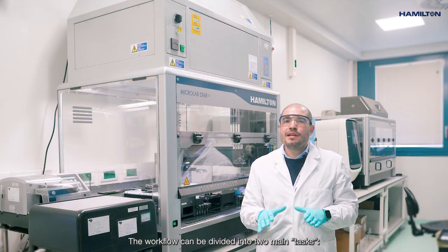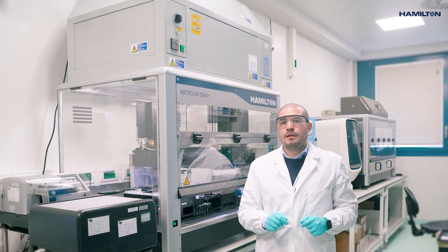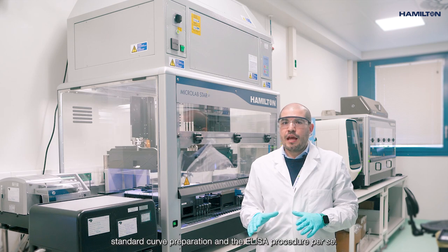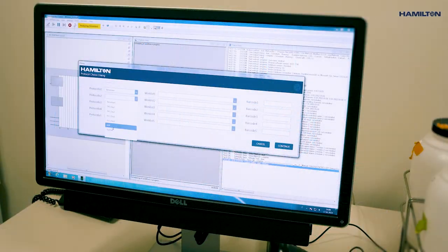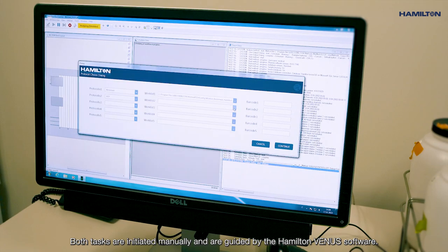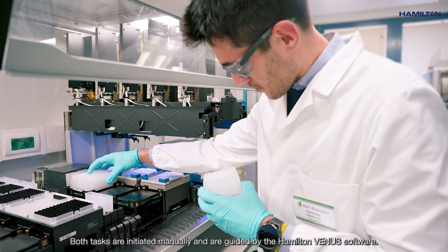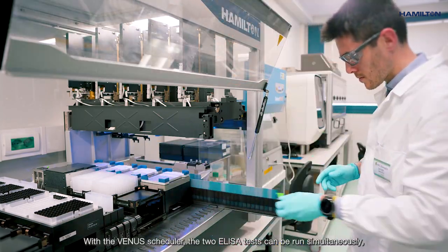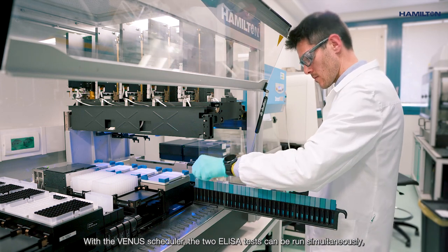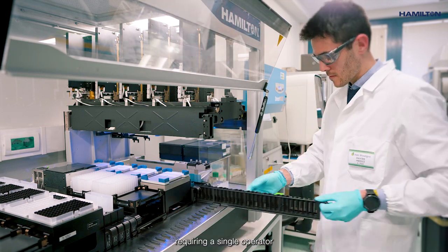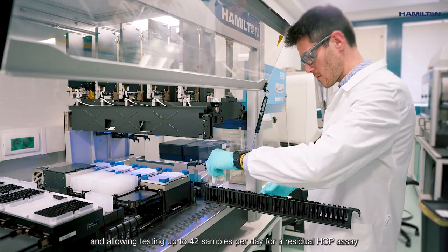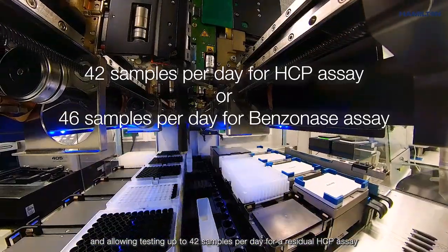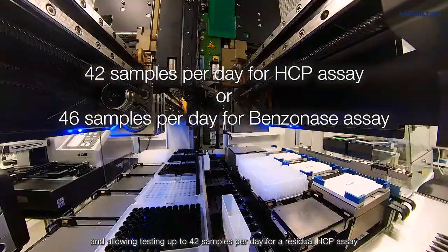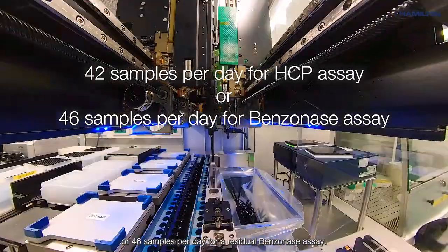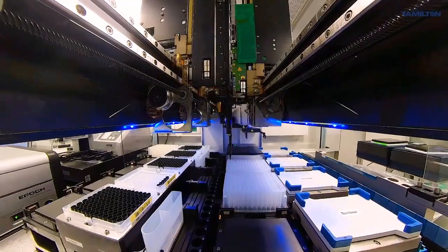The workflow can be divided into 2 main tasks: standard group preparation and the ELISA procedure itself. Both tasks are initiated manually and are guided by the Hamilton Venus software. With the Venus scheduler, the 2 ELISA tests can be run simultaneously, requiring a single operator and allowing testing up to 42 samples per day for a residual HCP assay or 46 samples per day for a residual benzonase assay.